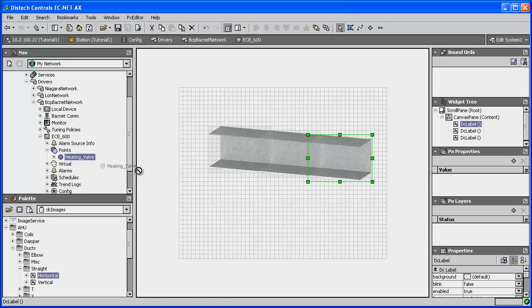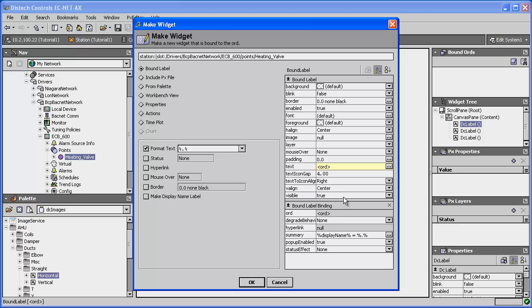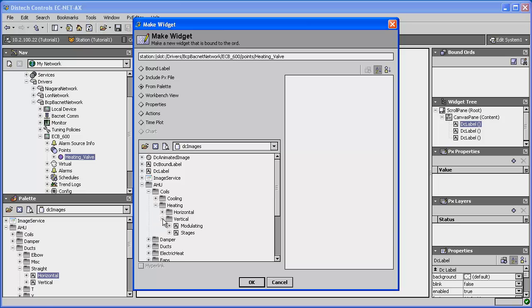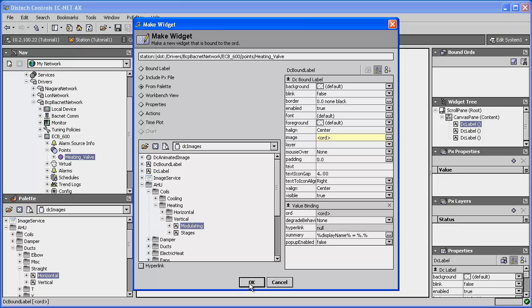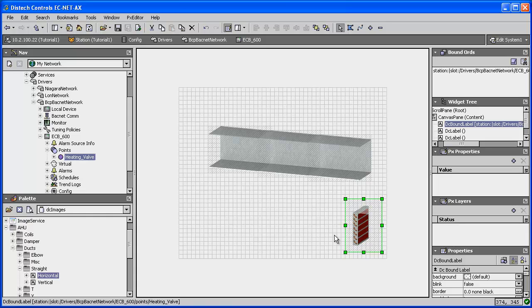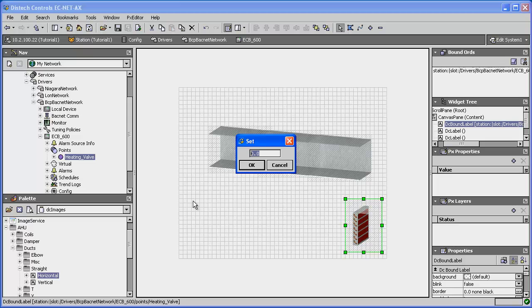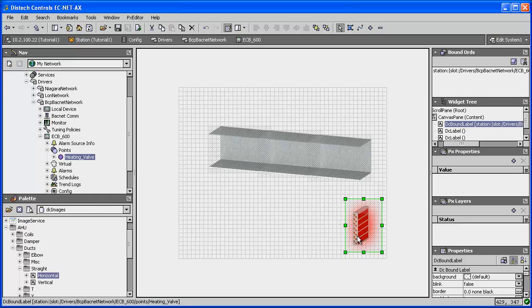I will drag and drop the new point onto the graphics page. The Make Widget window is displayed — this is where I will select the actual coil image. I will select From Palette and then select the coil I wish to add: a vertical modulating coil. The image is then displayed on the graphics page. To set a value to my image, I will right-click on the control point and select Actions, then Set, and put 100% heating. Notice how the glow of the coil intensified? That is because the coil image is an animated image and therefore it changes accordingly to show that the coil is at 100% heating.